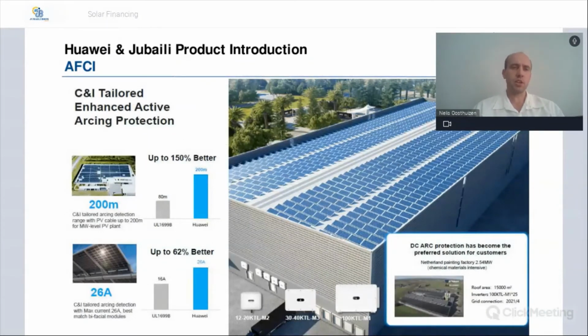Quickly mentioning, on the Huawei inverters they've got built-in AFCI protection, which is arc fault circuit interruption. We all know DC is a very dangerous voltage with quite high arcs. Huawei inverters are up to 150% better than the standard. The standard for AFCI is UL1699B, which requires detection up to 80 meters. Huawei is 150% better, we can detect up to 200 meters.